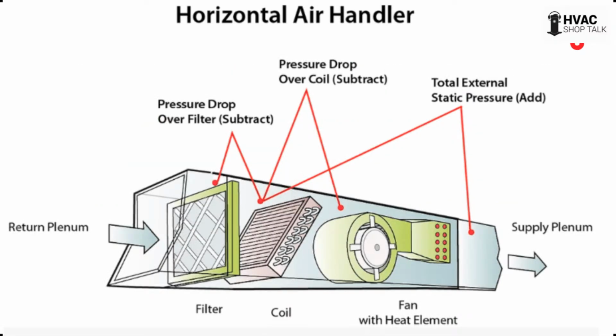On the screen, I have a horizontal air handler pictured. You have the return plenum, a filter, a coil, the blower section, and the supply plenum. When I say static pressure, you're measuring total external static pressure. And in this particular slide, and I'll describe it for the podcast, folks, one of the probes is out in the supply plenum, and another probe is between the filter and the coil.